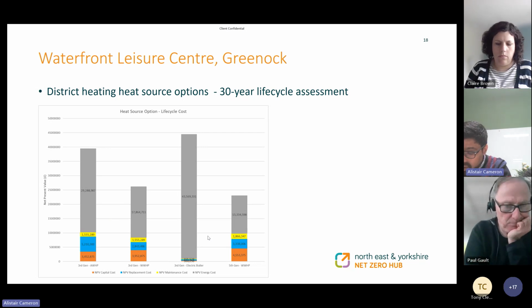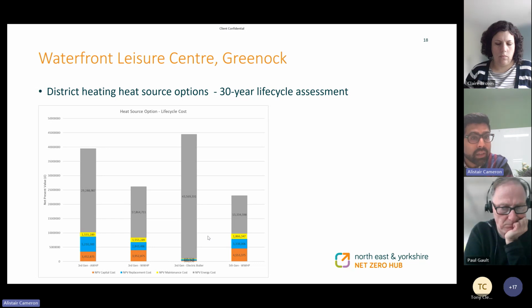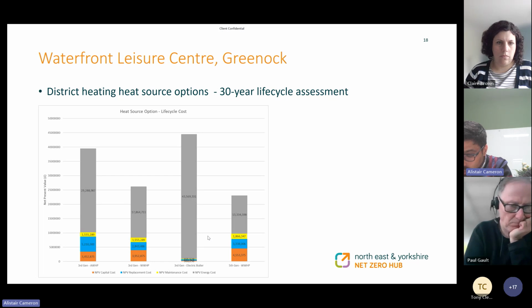The air source heat pump was number 3 in terms of performance. You had a relatively high capital cost, but you do have to replace the technology over that 30-year period. So typically air source heat pumps might only last 15 to 20 years before the actual heat pump needs replaced. Therefore, we have to account for that replacement. There's also maintenance costs. However, when you compare the operational running costs with electric boilers, it is significantly less. So it goes from electric boilers at 43 million compared to 29 million for the air source heat pumps.